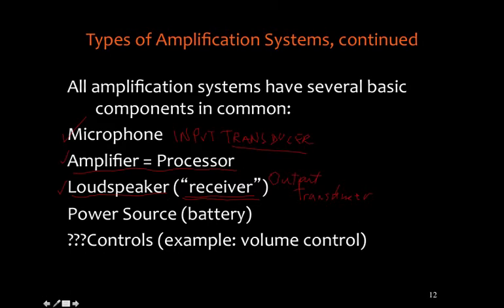In most cases, but not exclusively, the output transducer is going to be a device that changes energy into an acoustic signal, and that would be this speaker kind of thing. Now, there are other alternatives for output transduction. If it's turning it into sound waves, then it's creating an air-conducted signal. It's also possible that the output might be vibration, which would go to some kind of bone conduction device. So technically speaking, there are air conduction types of hearing aids and bone conduction types of hearing aids.